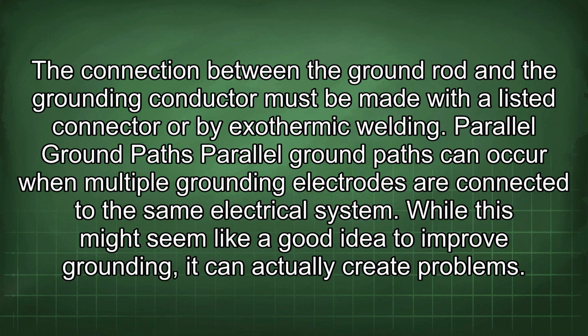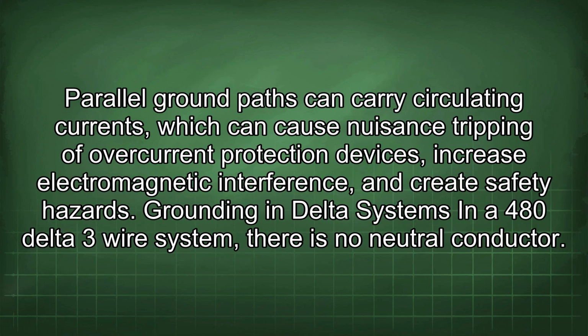Parallel ground paths. Parallel ground paths can occur when multiple grounding electrodes are connected to the same electrical system. While this might seem like a good idea to improve grounding, it can actually create problems. Parallel ground paths can carry circulating currents, which can cause nuisance tripping of overcurrent protection devices, increase electromagnetic interference, and create safety hazards.